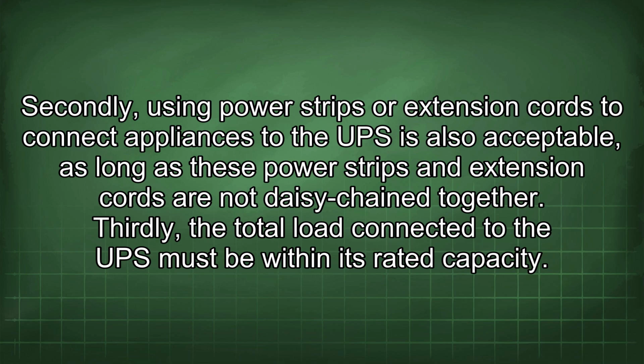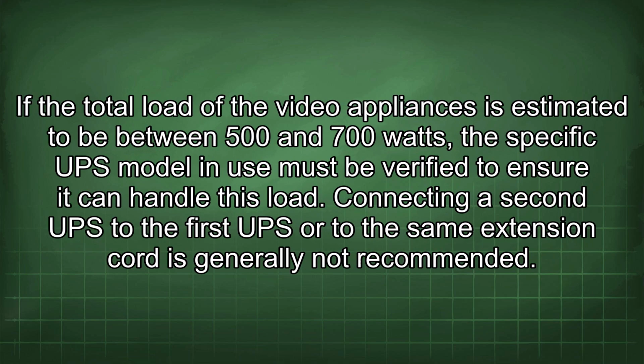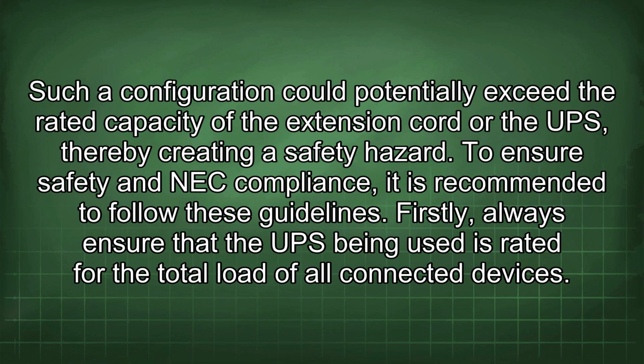Thirdly, the total load connected to the UPS must be within its rated capacity. If the total load of the video appliances is estimated to be between 500 and 700 watts, the specific UPS model in use must be verified to ensure it can handle this load. Connecting a second UPS to the first UPS or to the same extension cord is generally not recommended. Such a configuration could potentially exceed the rated capacity of the extension cord or the UPS, thereby creating a safety hazard. To ensure safety and NEC compliance, it is recommended to follow these guidelines.